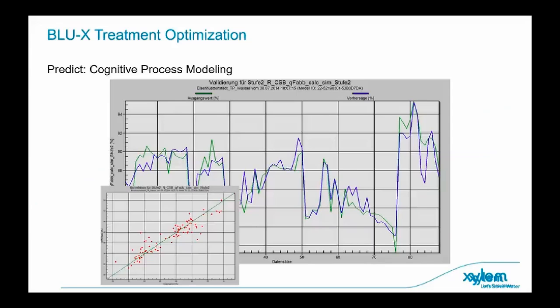So once you've got that model trained, you can then start to read the influent information, know what targets you need to hit as the effluent, and then run through hundreds of thousands of different treatment options, if you like, so different set points, different blower intensities, whatever the process is that you're looking at, in a matter of seconds, and come up with the optimum solution, the most efficient, but meeting those strict criteria for effluent quality.